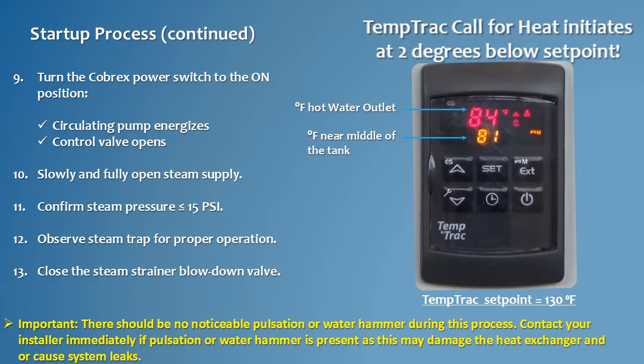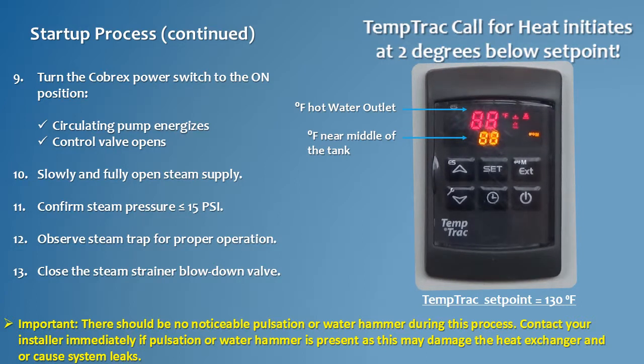Confirm the steam pressure entering the Cobrex heat exchanger is 15 psi or less. Observe the steam trap for proper operation. Now close the steam strainer blowdown valve. Important: there should be no noticeable pulsation or water hammer during this process. Contact your installer immediately if pulsation or water hammer is present, as this may damage the heat exchanger and/or cause system leaks.